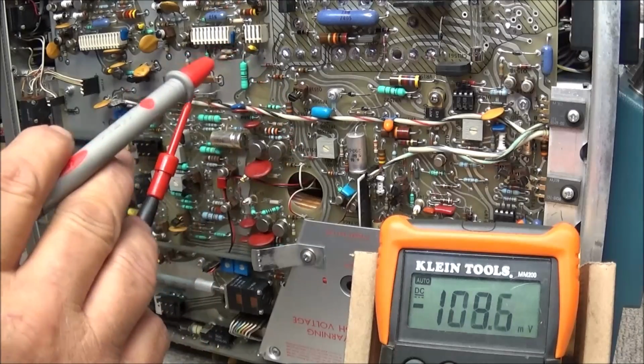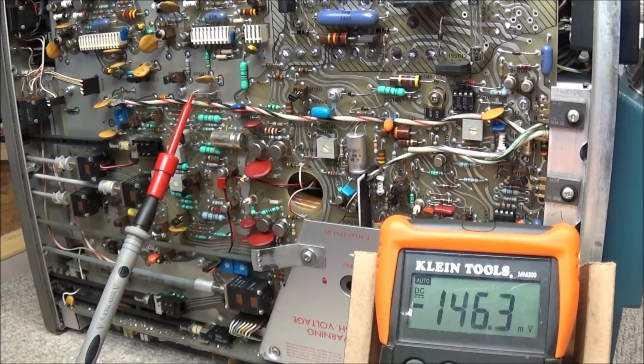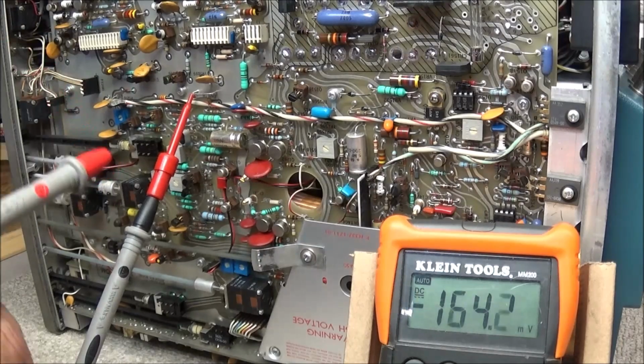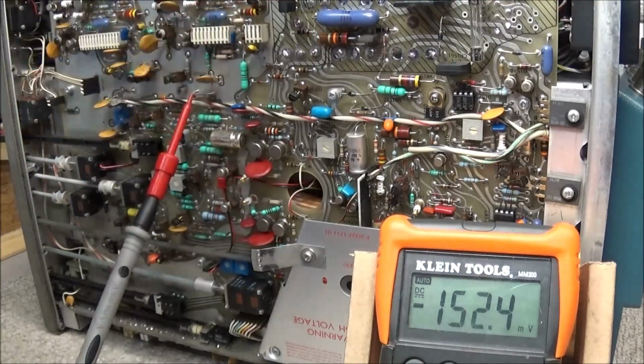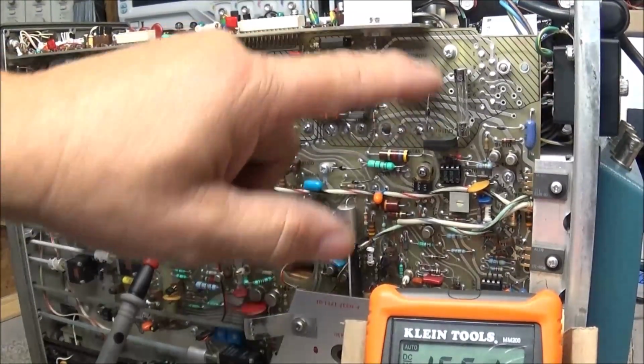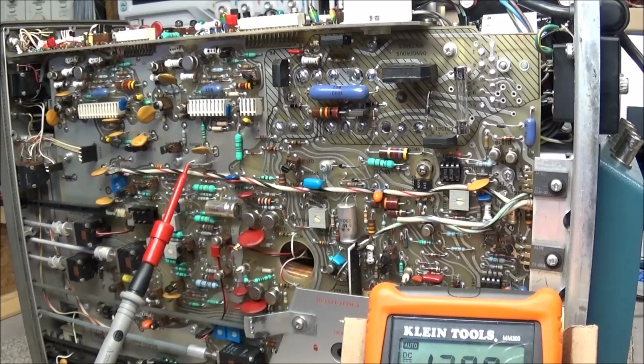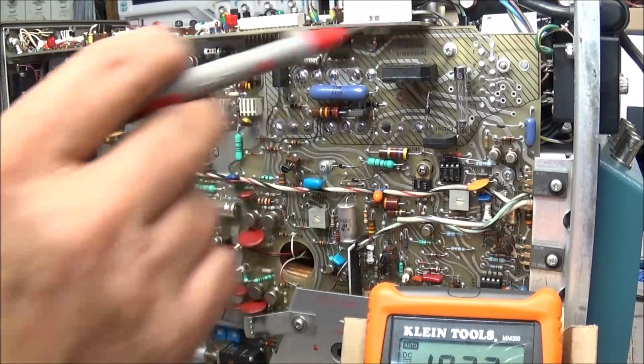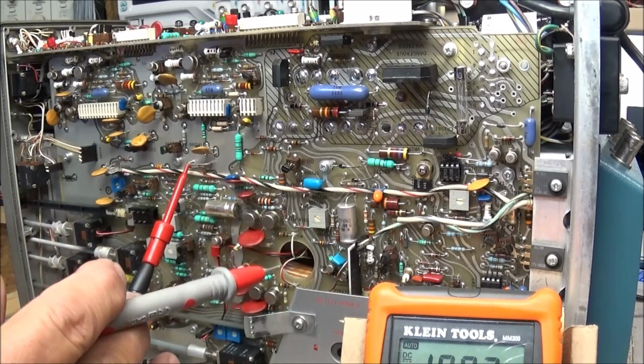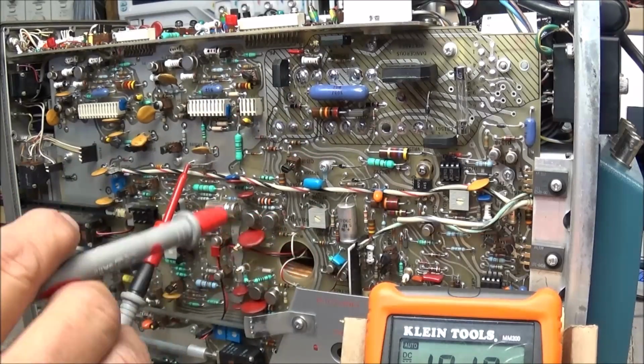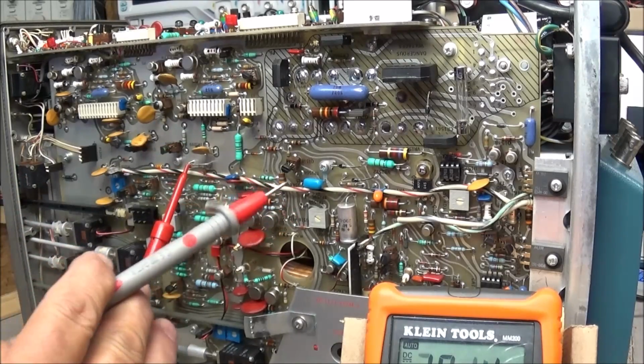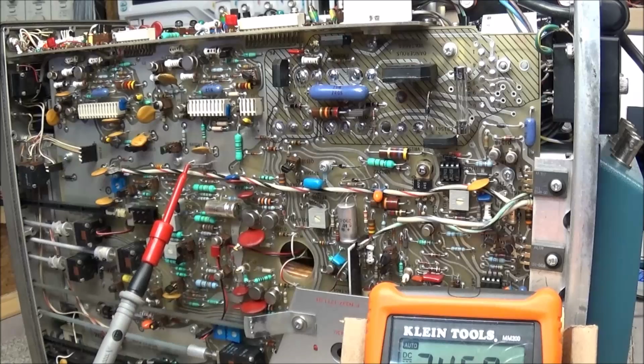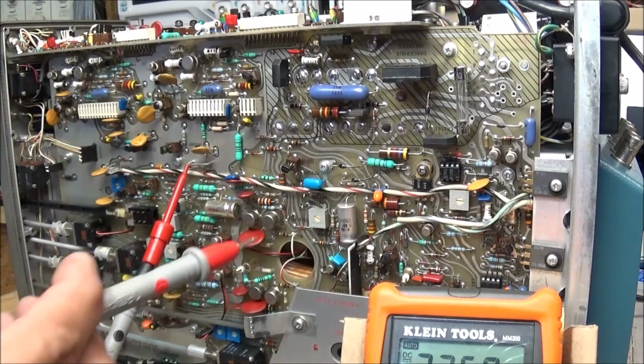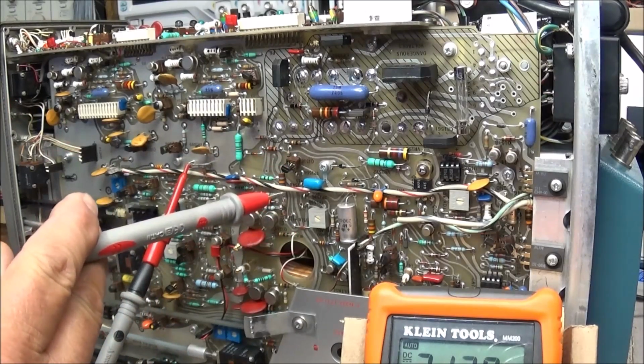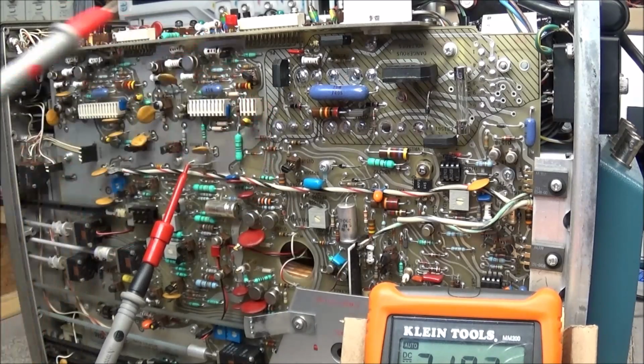So once you've done this and you've checked your voltages on those rails, you can always go up here to the bridge rectifiers and check your voltage off the bridge rectifiers and see if that's correct. And that'll tell you what is coming off the bridge rectifiers. The next thing you can do after you troubleshoot that is start isolating the supplies, lifting whatever's connected to it and going back and checking the supplies to see if you have full voltage. Then you can put a load on it, scope out the rail, and look at the voltage and the ripple on it.